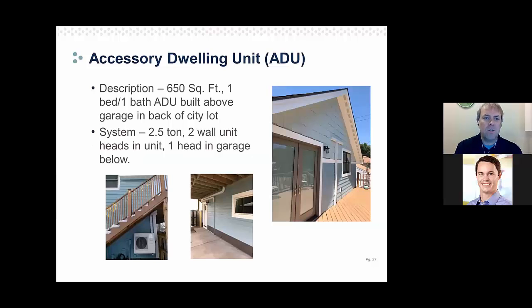First, this accessory dwelling unit, the ADU, is about 650 square feet. It's a one bed, one bath ADU built above the garage in the back of the city lot. The system is a 2.5 ton, with 2 wall unit heads in the unit and one head in the garage below. The client wanted some heat in their garage, so it's a little oversized for that compared to just the rest of the apartment or ADU.